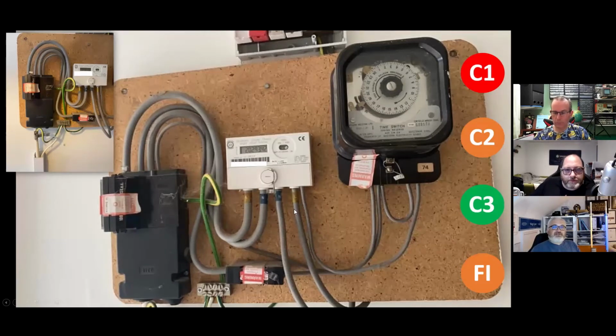However, did anybody spot the white painted cable that goes down the surface trunking? Can you see that? Going to throw more at you. This is quite a complex one. But there is a white cable. Please tell me, everyone, if you can see this. Where my arrow is, there is a white cable that comes out the connector block as well. Is it painted white or is it white? It's painted white. As you can tell, it's the same color as the walls. Right. So somebody's painted that. They've evidently renewed the green and yellow at some point.